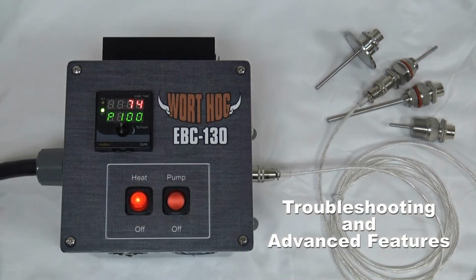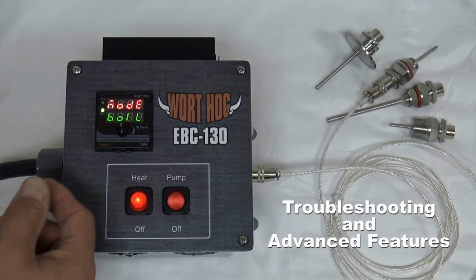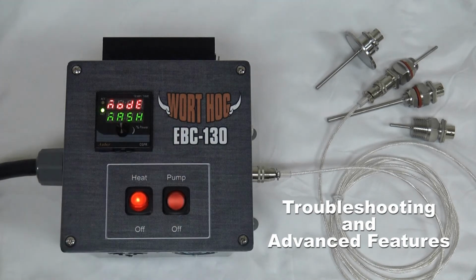We ship the controller with some of the advanced features disabled. This is so that the controller is most intuitive to use right out of the box. With timer functions disabled, the only menu choices displayed when you push the knob momentarily are boil and mash. If you have the timer enabled, you're going to see a timer reset menu as well. Timer functions are enabled or disabled with the TF parameter, and they're located in the system menu.